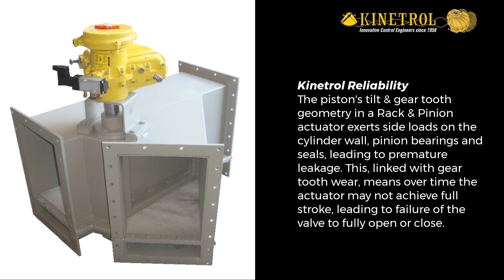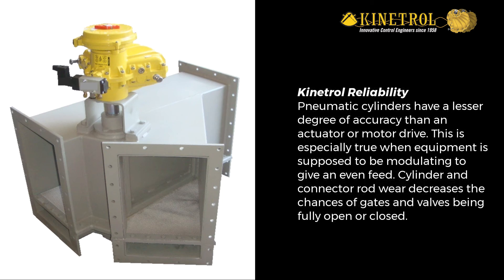This, linked with gear tooth wear, means over time the actuator may not achieve full stroke, leading to failure of the valve to fully open or close. Pneumatic cylinders have a lesser degree of accuracy than an actuator or motor drive, especially when equipment is supposed to be modulating to give an even feed.